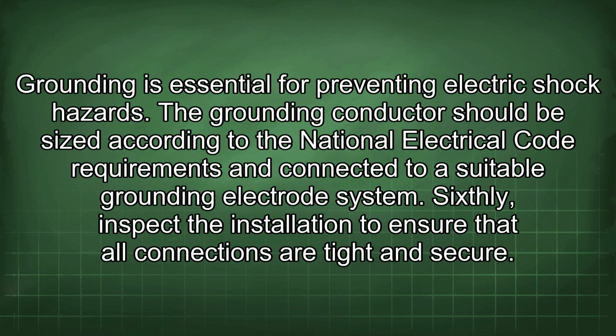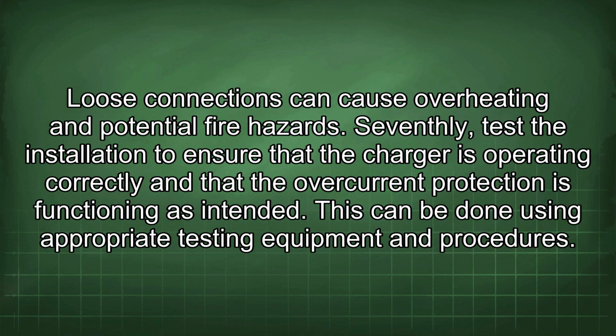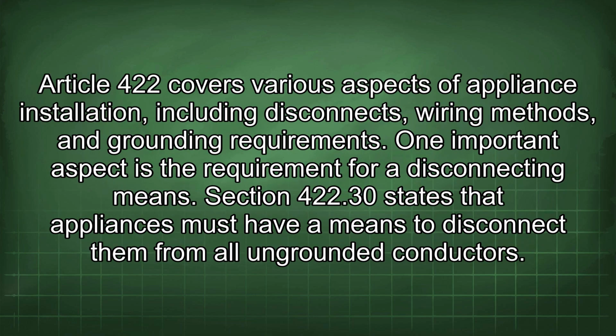Sixthly, inspect the installation to ensure that all connections are tight and secure. Loose connections can cause overheating and potential fire hazards. Seventhly, test the installation to ensure that the charger is operating correctly and that the overcurrent protection is functioning as intended. This can be done using appropriate testing equipment and procedures. Article 422 covers various aspects of appliance installation, including disconnects, wiring methods, and grounding requirements. One important aspect is the requirement for a disconnecting means.